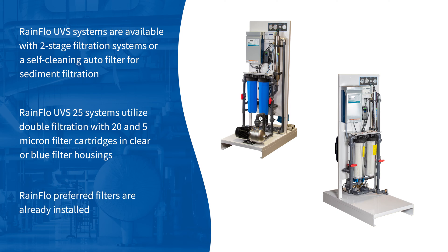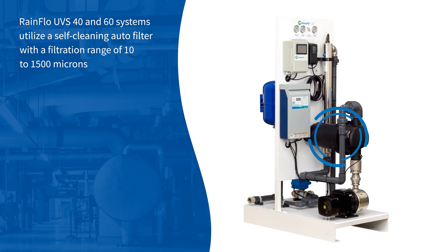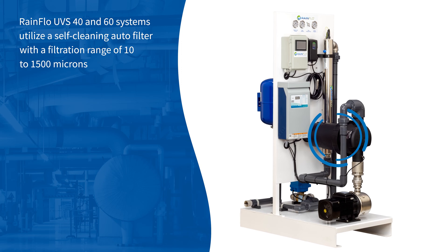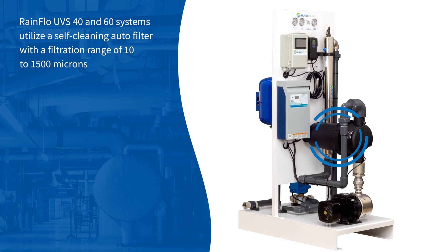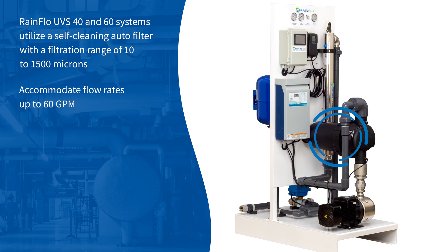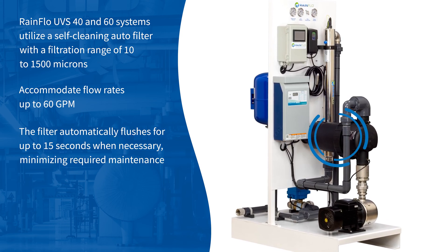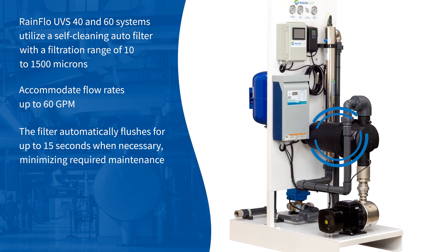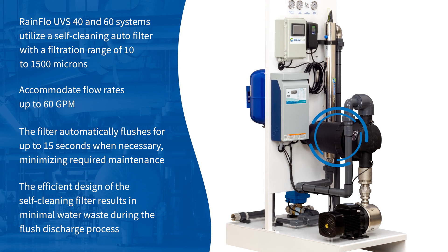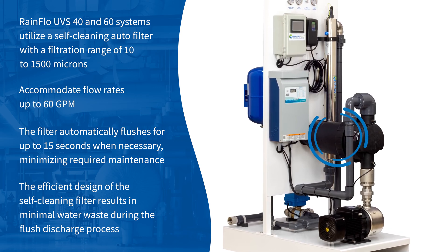RainFlo preferred filters are already installed. RainFlo UVS 40 and 60 systems utilize a self-cleaning auto-filter with a filtration range of 10 to 1,500 microns and accommodate flow rates up to 60 GPM. The filter automatically flushes for up to 15 seconds when necessary, minimizing required maintenance. The efficient design of the self-cleaning filter results in minimal water waste during the flush discharge process, while filtration is uninterrupted.